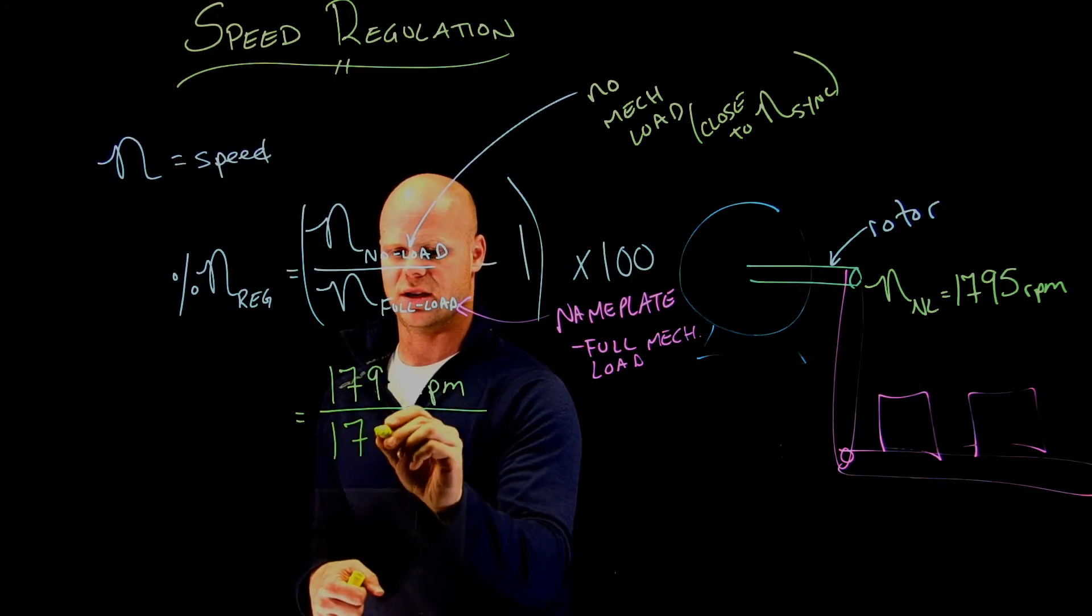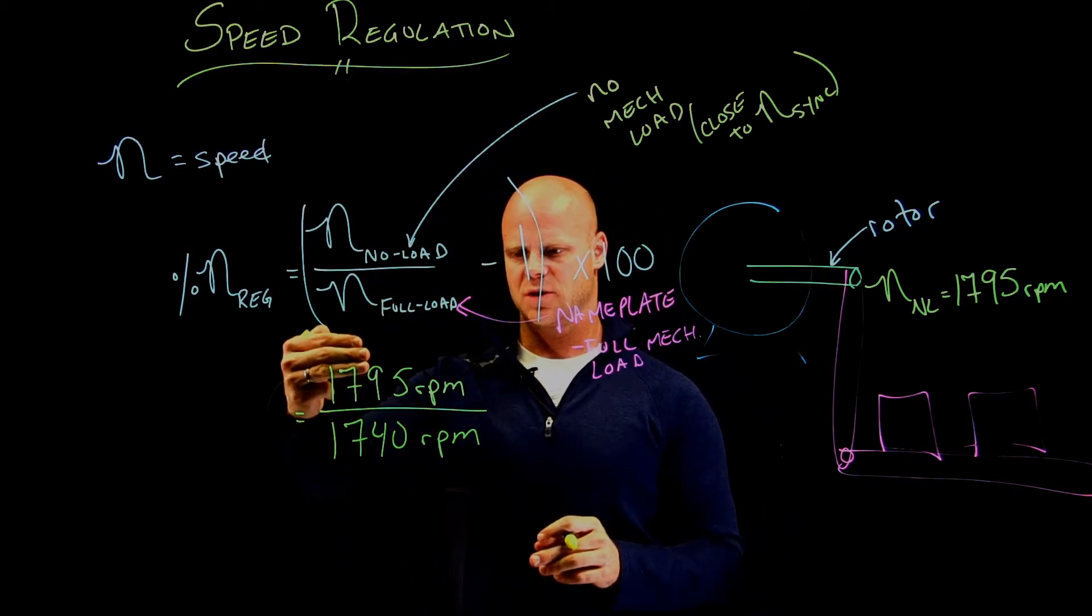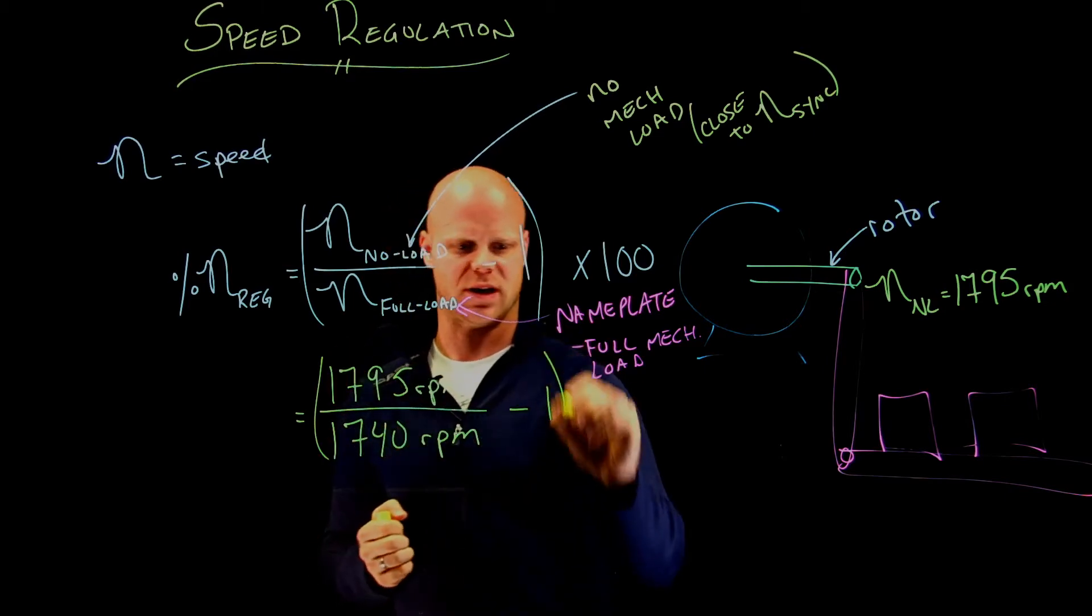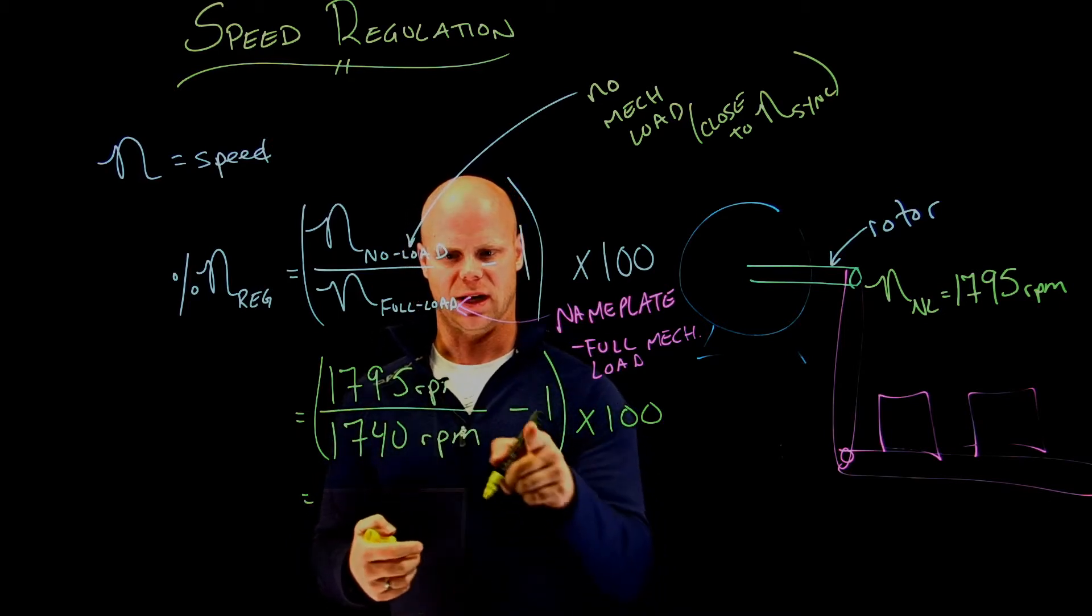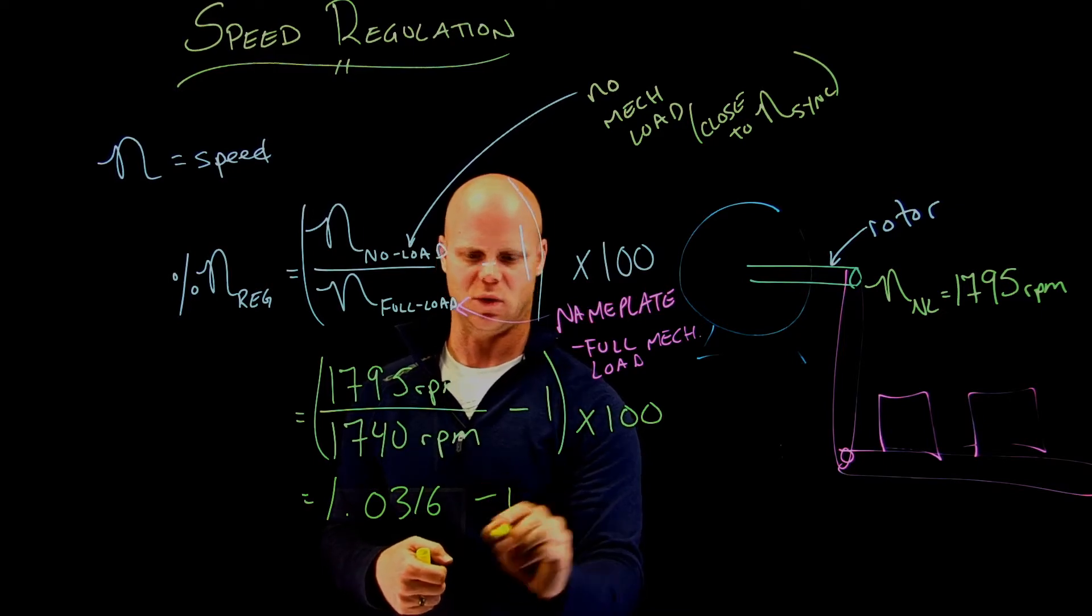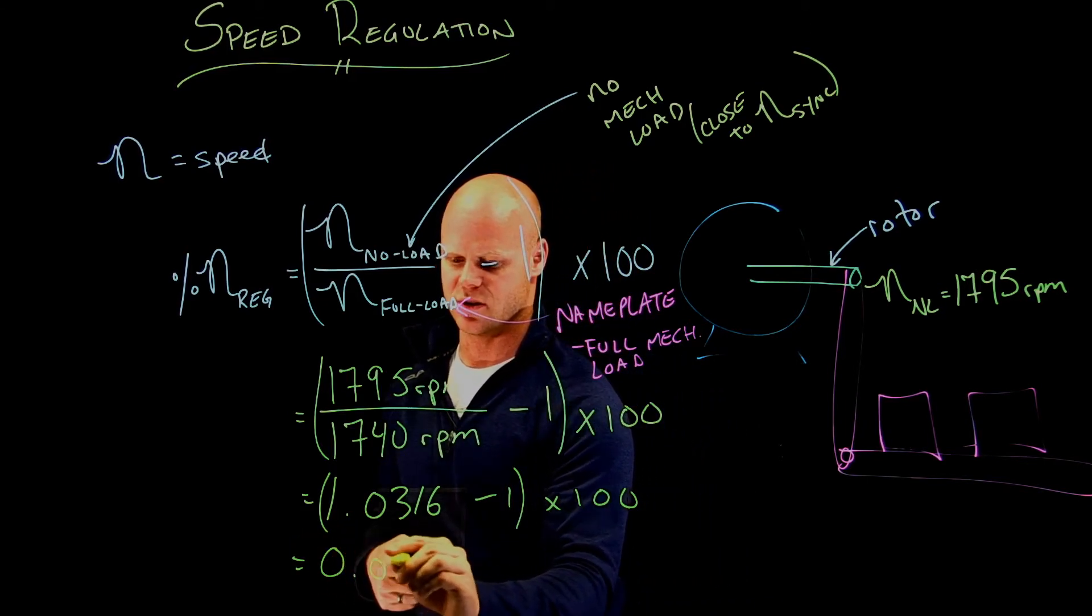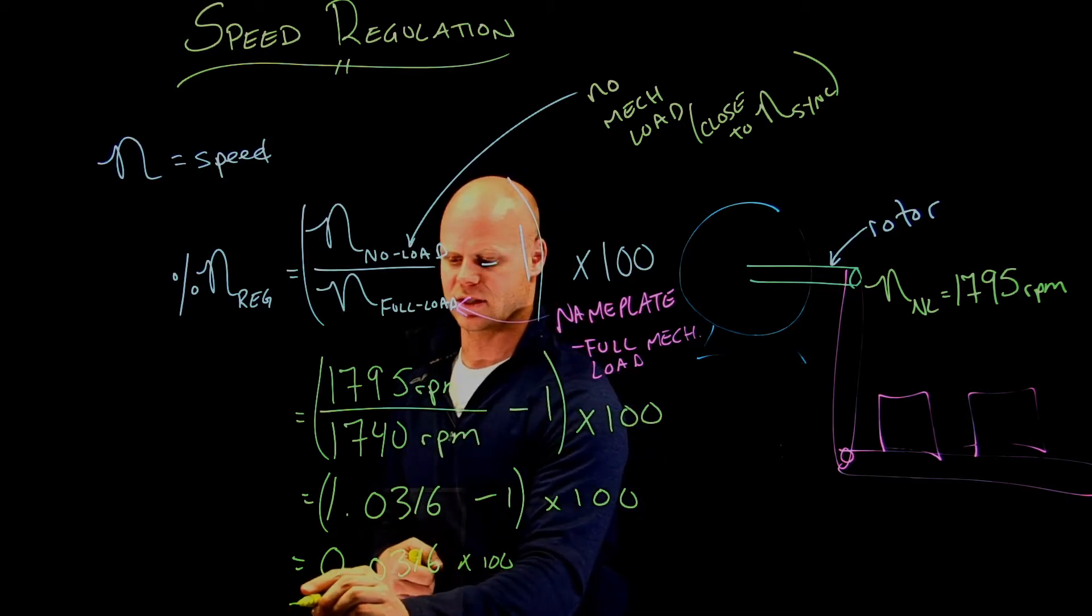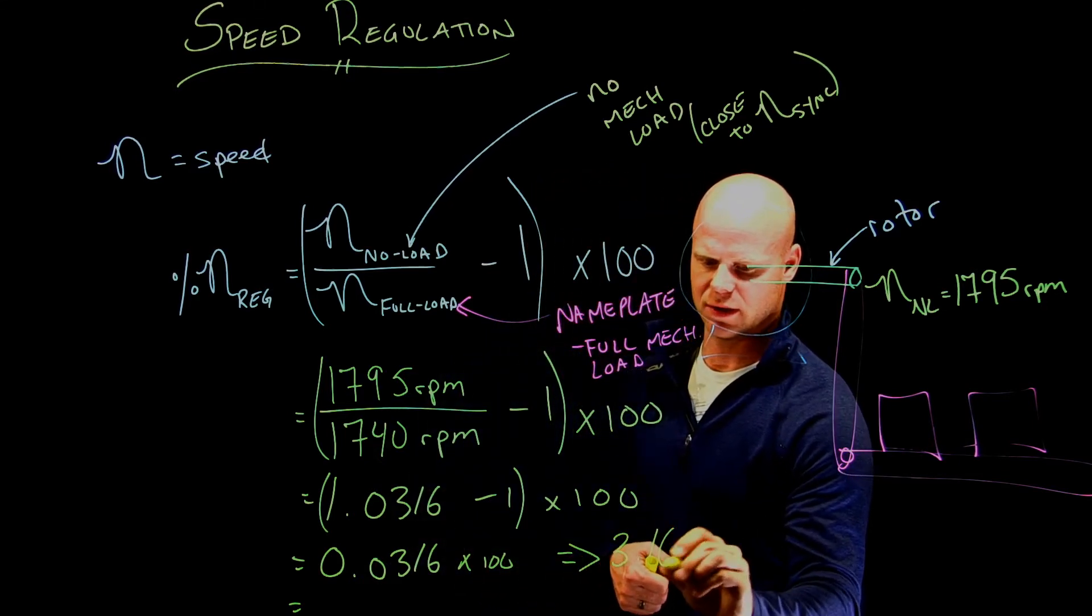As you look at this: my no-load speed is higher than my full-load speed—that's perfect—minus one, and we'll times this by 100 at the end. Really important that you remember the no-load speed is higher than the full-load speed. What you end up with: if you do this in the brackets, it's 1.0316 minus 1 times 100. So I get 0.0316 once I subtract the 1, times 100. Now this is expressed as a percentage: 3.16 percent.